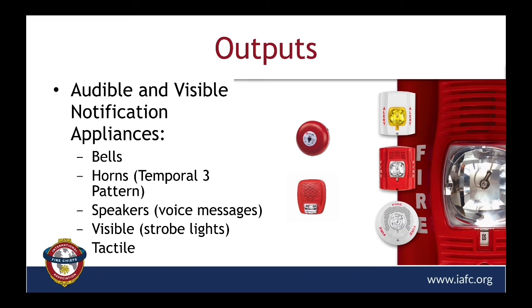Looking at horns, they are a notification appliance that alerts people by the sense of hearing. And they are required to produce a very distinctive temporal 3 pattern. So it's not just a constant alarm tone. It has a very distinctive temporal 3 pattern tone. Looking at speakers, they provide voice messages instead of the audible-only tone from horns. And speakers allow for pre-recorded or live voice instructions to be sent to certain areas of a building or throughout an entire building. And they are very good at sending messages as conditions in a building could change.